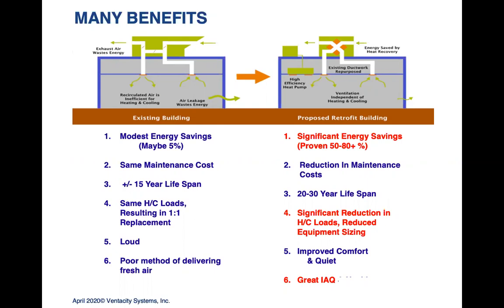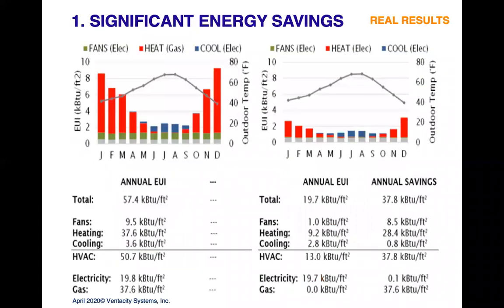This is the first project we did in Portland, Oregon. This is a 12,000 square foot office building. It had 9 4-ton RTUs on the roof, which represented about 36 tons of cooling capacity. And so it had an EUI on the building of 50.7 when we started.